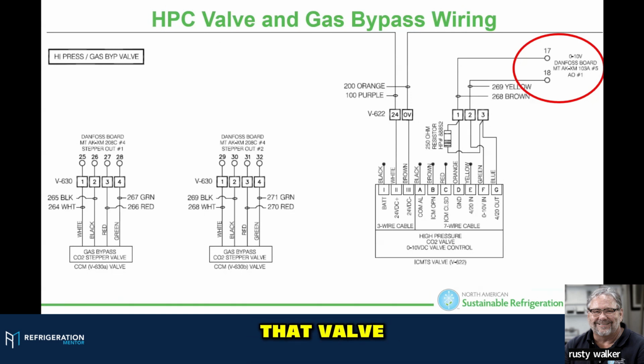And every time that valve moves, I'll see it switch from negative to positive - -3, +3, -3, +3. Sometimes it'll go positive. If I'm close to set point, it's not going to send a signal, so I'm rarely going to see that movement. If I'm suspecting something's wrong, I can simply go into the controller and change the set point so that I can force this valve to drive to a new position, and I'll see it go -3, +3, -3, maybe -4, maybe -5, whatever. But I can see it moving.